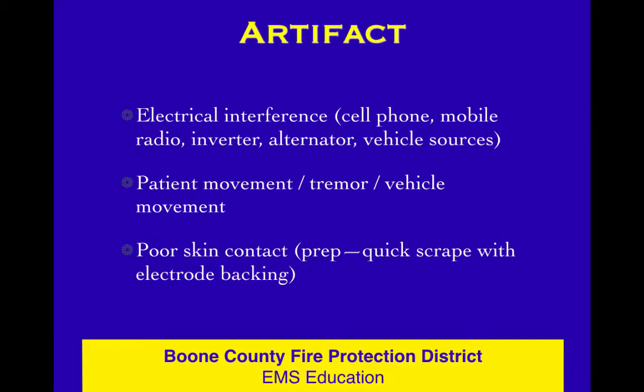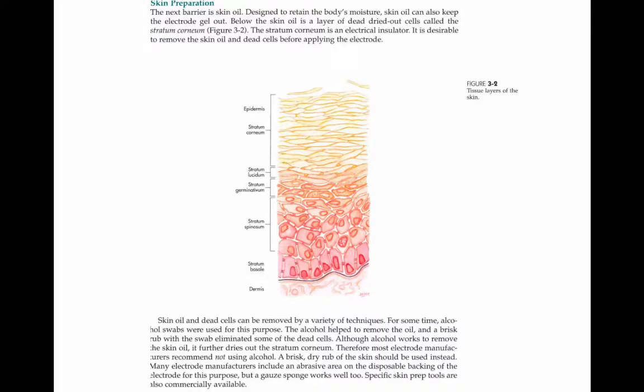Many times we don't even do the most cursory quick prep of the skin. If you will just take that plastic backing that your sticky electrode comes with out of the package, put the wire on the electrode, peel the electrode off, and then take that little piece of plastic and just quickly scrape where you're going to put the electrode — it will make a huge difference. Just get a little bit of that dead skin and skin oil off. There's also sweat, blood, and dirt. At least there's a layer of dead skin and some oil on almost all of us, so just scrape it real quick.